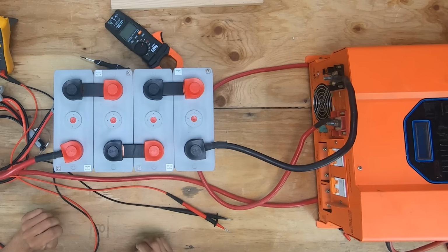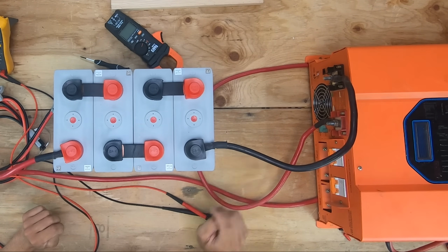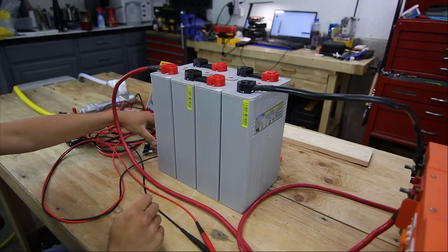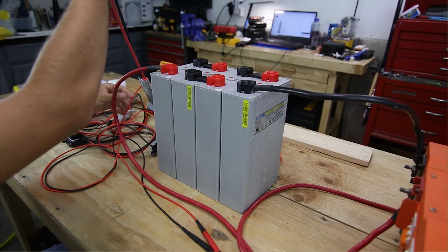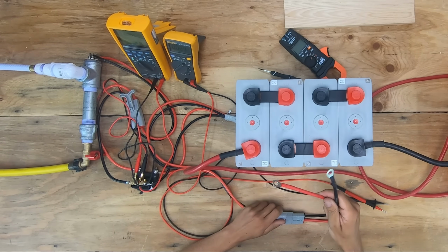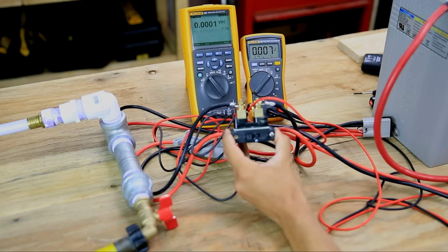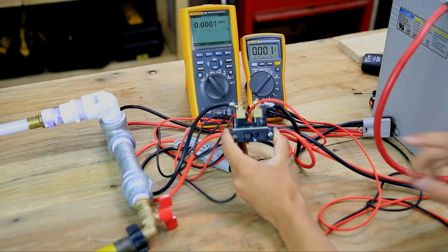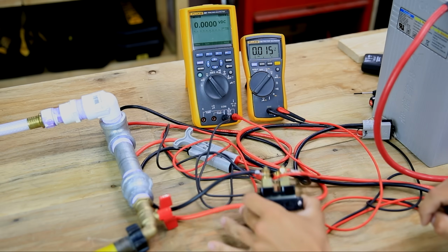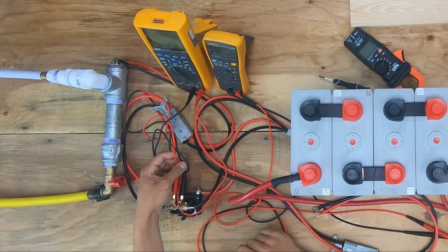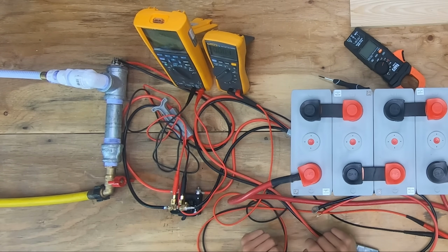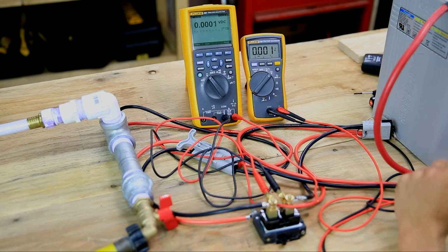So today we're going to be capacity testing them. The first thing I need to do is disconnect my inverter, and then I have a cable with Anderson connectors here that I can connect on. Then I have a circuit breaker shunt combo, so I can use the circuit breaker to start the test, connected with some leads to my Fluke 287, which I'm going to use as a logging multimeter to log the amps going in and out of the battery - in this case, only going out.